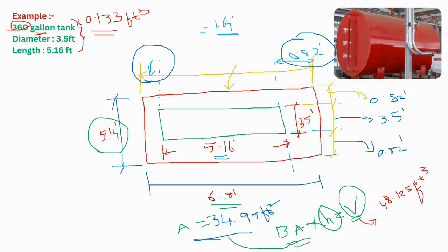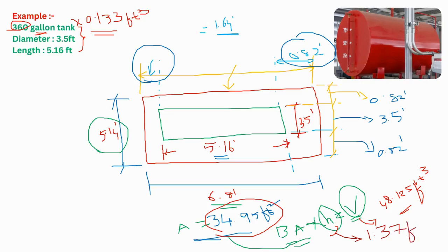Now we know the area and we know the volume, so it is easy to calculate the height. If you divide volume by area — 48.125 divided by 34.95 — we are going to get the height of the bund wall, which is about 1.37 feet.